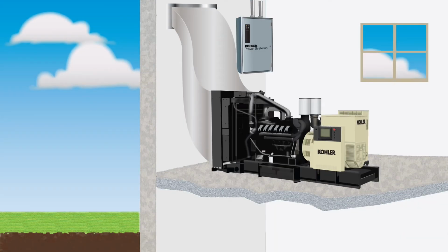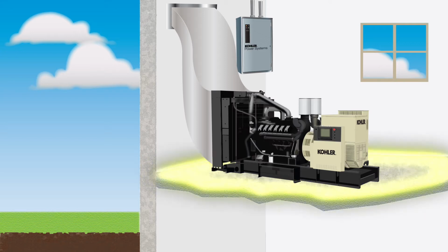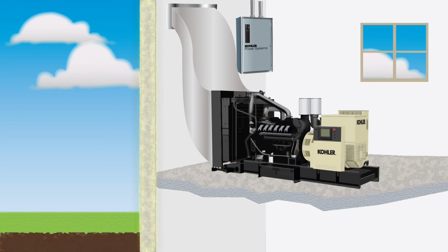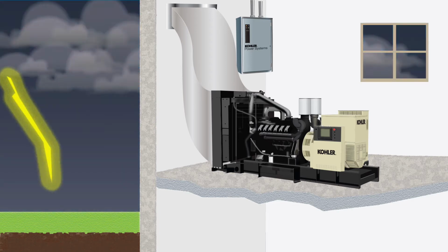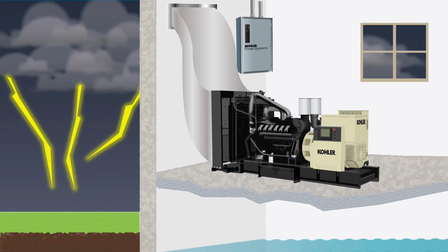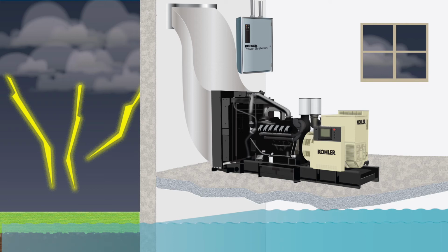FEMA recommends a generator system and its fuel supply is installed no lower than the ground floor and on concrete plinths above projected flood levels. In addition, the generator should be firmly anchored to the concrete with adequate space to walk around for maintenance. The building's walls should be strong enough to protect from hurricane-force wind and windborne debris. When a strong storm system creates flood conditions and strong winds stir up debris, the generator will be protected and able to supply power even when the utility is knocked out.